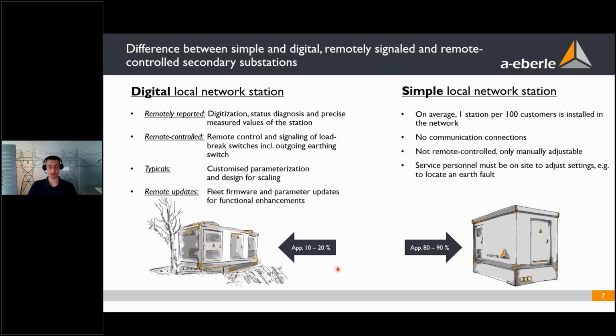And in order to handle this as a grid operator, you will need to manage your grid intelligently. It was estimated by grid operators that are in a development partnership with us that you would need about 10 to 20% of your local network stations to be digital, and about 80 to 90% of your local network stations to be simple in order to achieve a sufficiently intelligent grid. Of course, from a technical point of view, 100% intelligent or digital local network stations would be perfect, but there's also the economical factor to be considered.